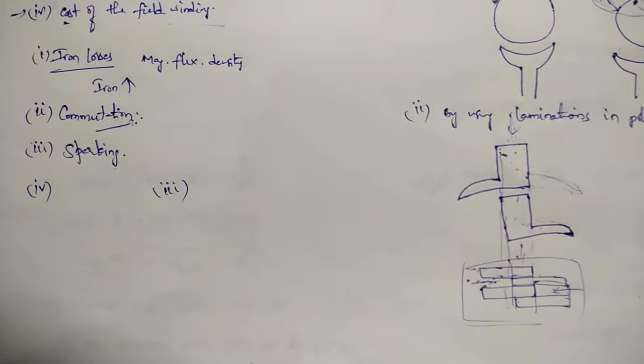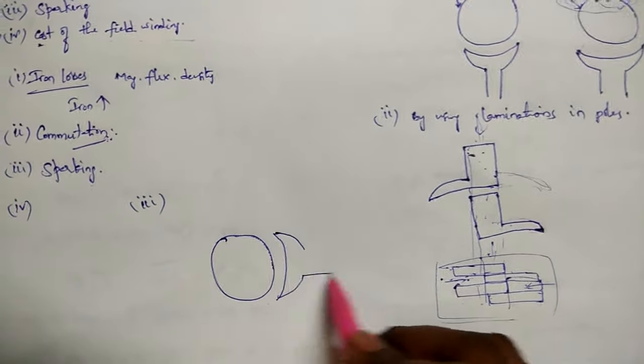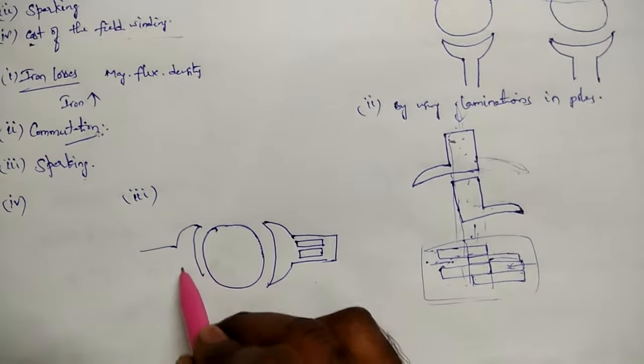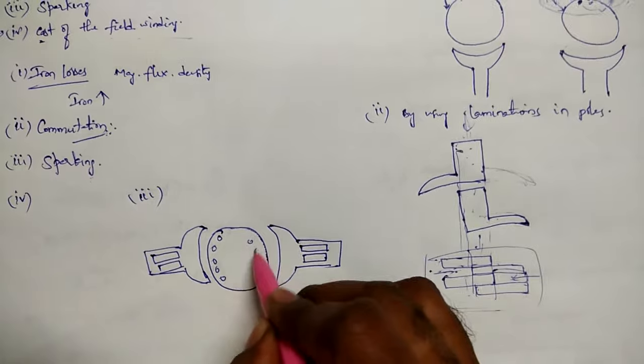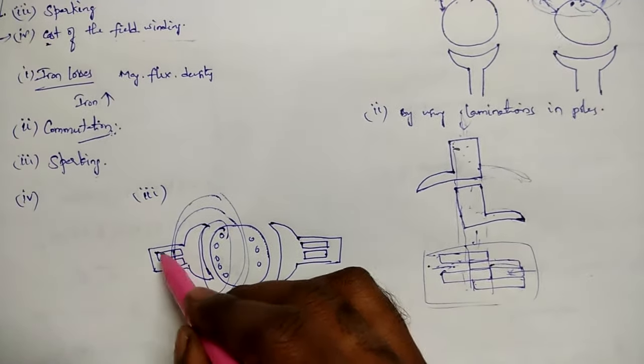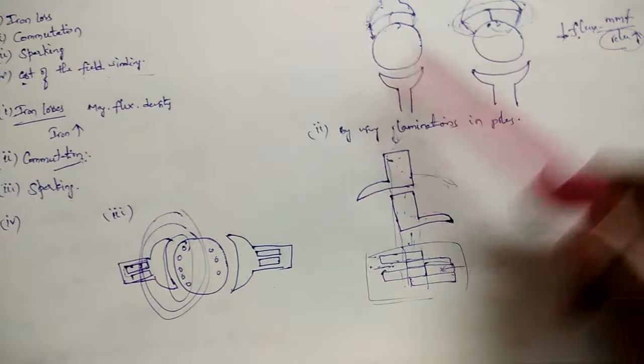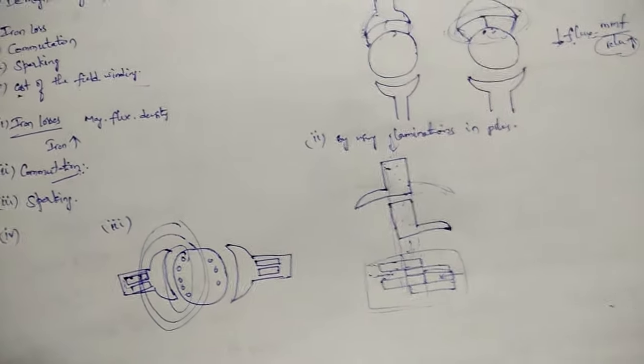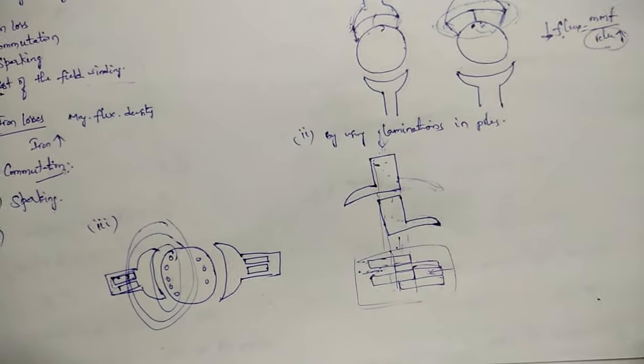The third method is by making rectangular holes in the poles. The armature flux passes through these holes, but since air fills them, the reluctance is higher, so the armature flux is reduced. The combination of these three methods — cambered poles, laminations, and rectangular holes — makes the armature flux more reducible, reducing the effect on the main field flux and thus reducing the armature reaction.